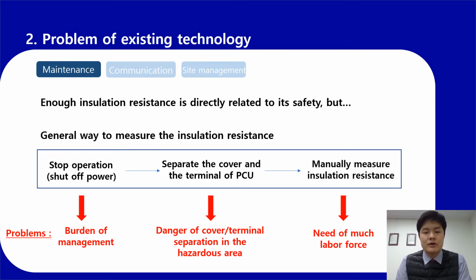But power shutoff can have negative impacts on the operation of the power plant. So it gives a big burden to the manager of the site. And many areas in the power plant are hazardous areas. Opening the cover and separating the terminal in a hazardous area is very dangerous. Moreover, when a person manually measures insulation resistance one by one, it requires a huge labor force. So, in reality, the checkup is done only once a year in the shutdown period.